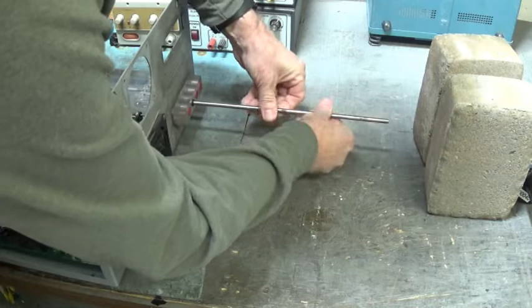Grab this wooden block right here, and I'm going to push that against the output connector of the charge master so we have good electrical contact. Now let's plug it into the wall. Once we're plugged into the wall, we do not touch anything inside this charge master. Even when the 120 volts AC is turned off, we don't risk it.